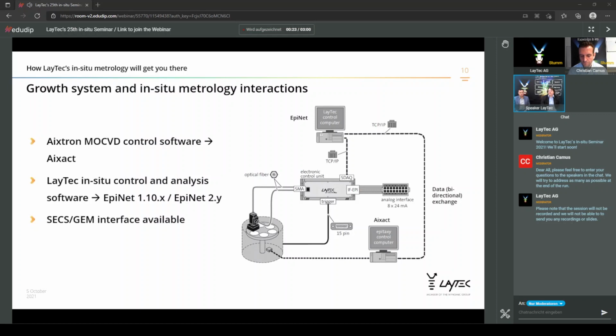So, this slide shows the basic, general, low-level technology integration map of how the epicurve TT system, running on the EpiNet software system, is implemented in a typical Aixtron MOCVD process setup. The core unit in terms of epicurve TT function is the LayTec controller. That's the center unit you see in the diagram to the right. It's a 19-inch controller that mainly holds the main hardware providing the technology functions needed for the epicurve TT system. The main control instance to control the MOCVD process itself is the epitaxy control computer to the right and in the bottom area.